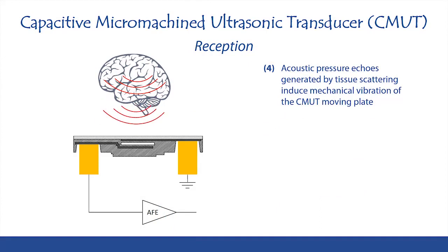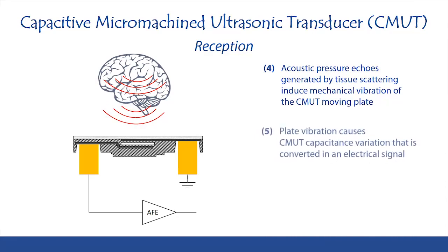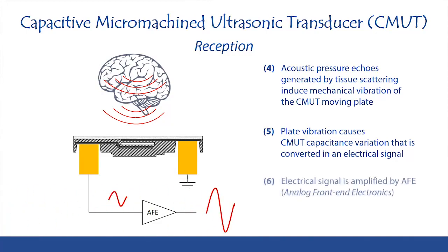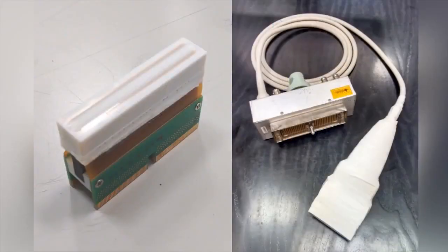Acoustic waves generated by tissue scattering cause vibrations of the moving plate that change the capacitance of the CMUT cell. This produces an electrical signal which is further amplified and transmitted to the ultrasound system.